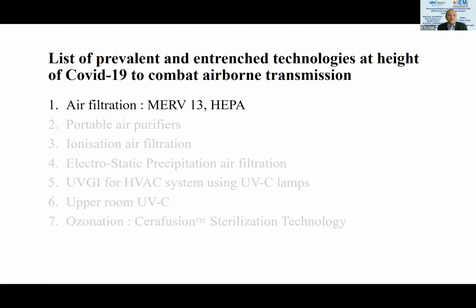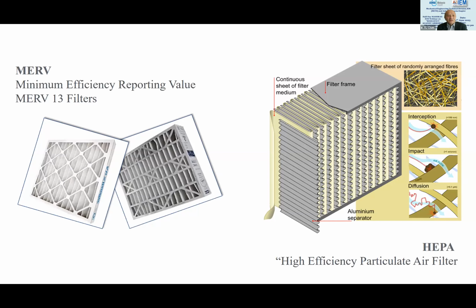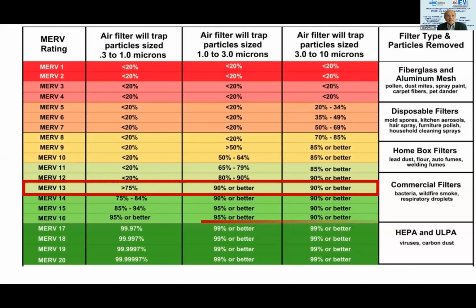First on the list, and it's actually not new, is good filtration, as Dr. King mentioned. Many of us have moved on to MERV 13 filters, or even MERV 14, or right down to HEPA. Here's a quick snapshot of what these filters look like and why MERV 13 matters: it can capture particles down to 0.3 to 1 micron in size, with efficiency of over 75% and over 90% for larger particles. If you move from MERV 13 to 14 and beyond, as the earlier curve showed, it plateaus off, so there's little extra advantage but you pay more, unless you go all the way to MERV 17 and above, the HEPA range, with performance up to 99.999%, or what we call H13.